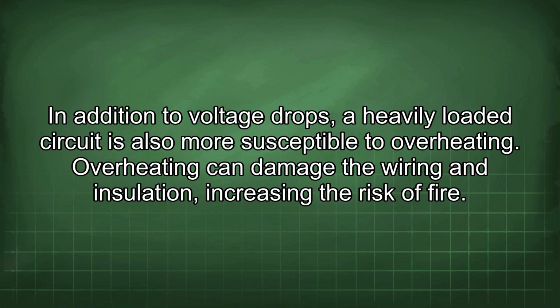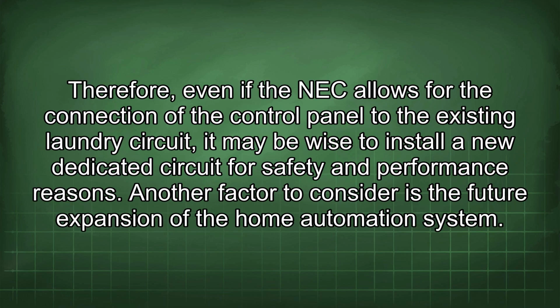In addition to voltage drops, a heavily loaded circuit is also more susceptible to overheating. Overheating can damage the wiring and insulation, increasing the risk of fire. Therefore, even if the NEC allows for the connection of the control panel to the existing laundry circuit, it may be wise to install a new dedicated circuit for safety and performance reasons.